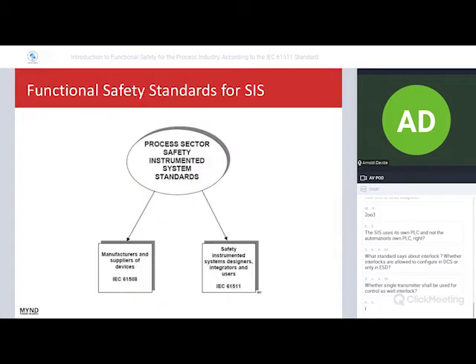We have two different standards for functional safety in the process industry. The first one is 61508. It is the standard addressed to the manufacturers and suppliers of devices. The second standard is 61511, and it is related to designers, safety instrumented system integrators and end users of the process plant. Anyway, if you are a designer, for example, you have to realize the SIS using components compliant with 61508.